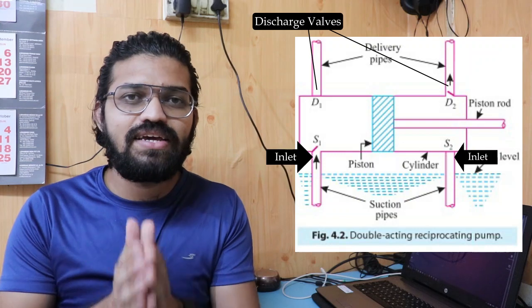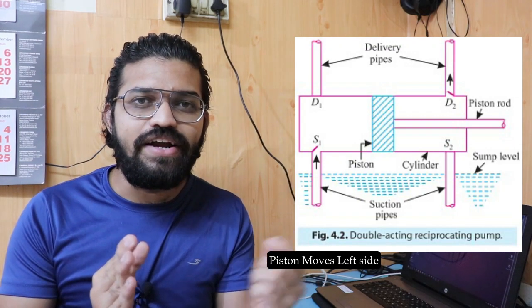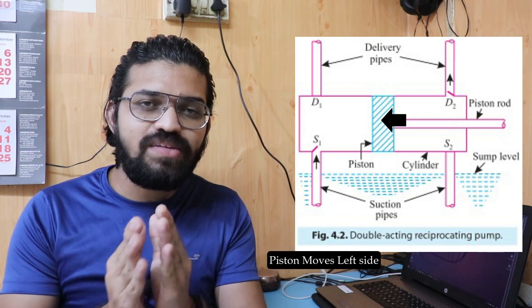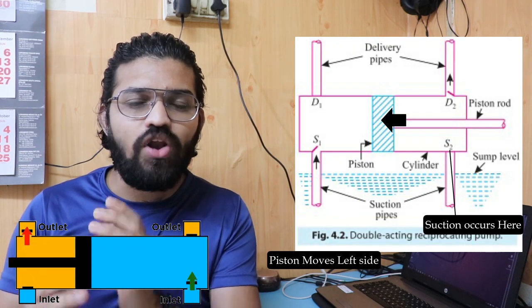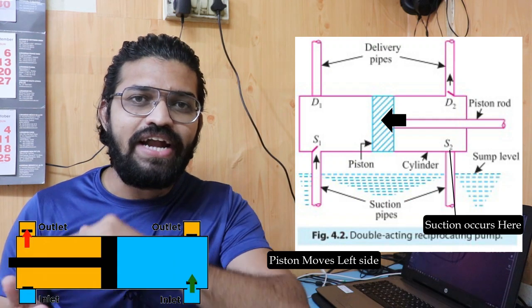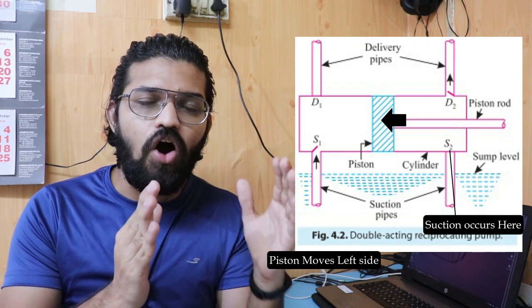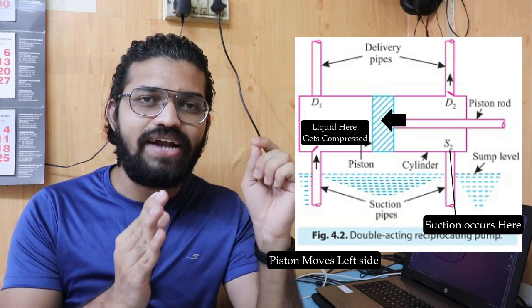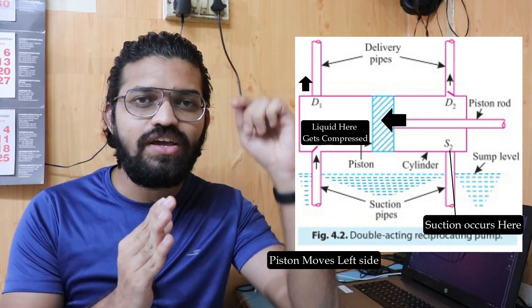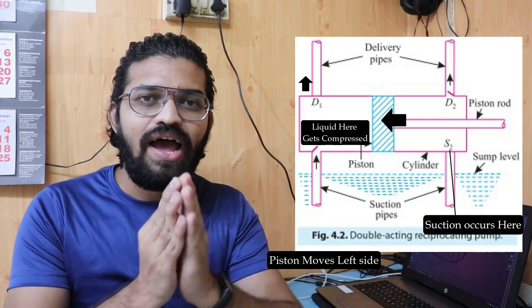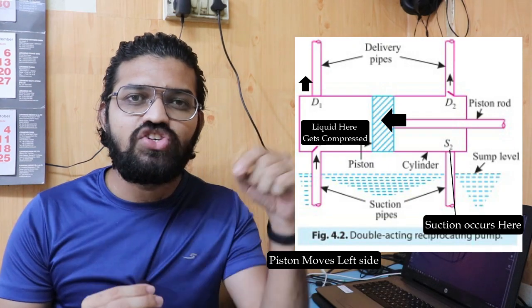As the piston reciprocates — scenario one: the piston moves towards the left side. As it moves left, suction is created at the back side of the piston and the inlet valve at the back side opens. Liquid enters the cylinder, and at the same time the liquid on the left side of the piston gets pressurized. The delivery valve on the left side opens and liquid is discharged through that discharge valve.